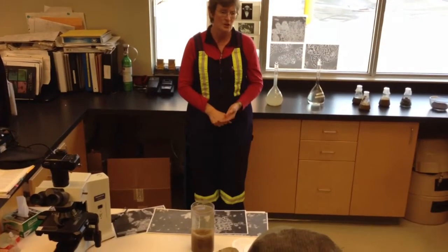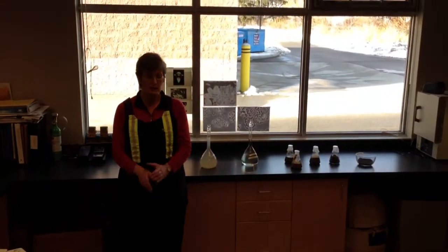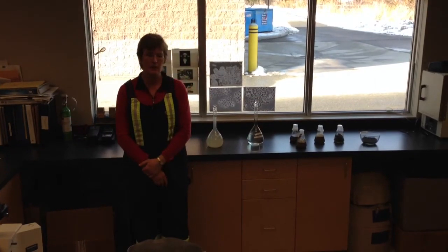Maybe your oxygen is too low or too high, or it's not really something that you can control. It tends to be each plant. Probably Kelowna has a different look to the sludge. Their sludge may be a darker chocolate color, but that may just be the nature of the plant.